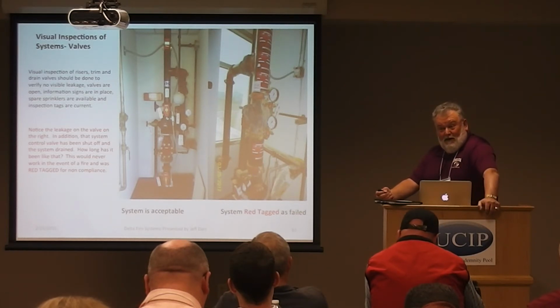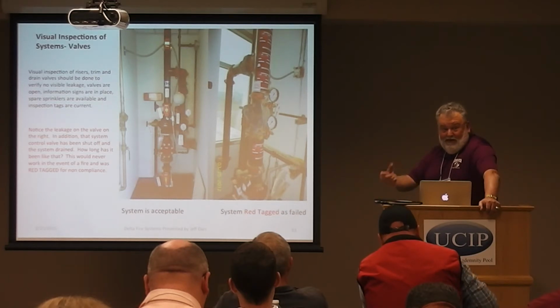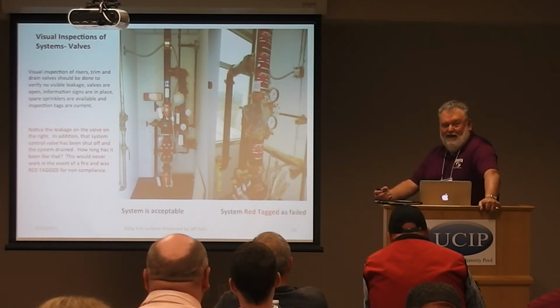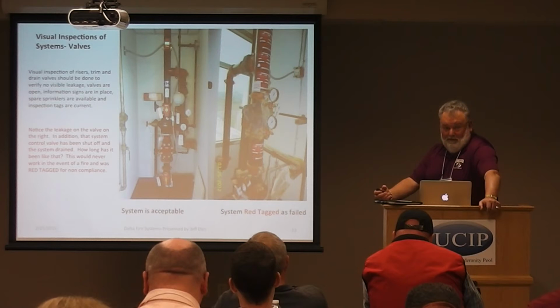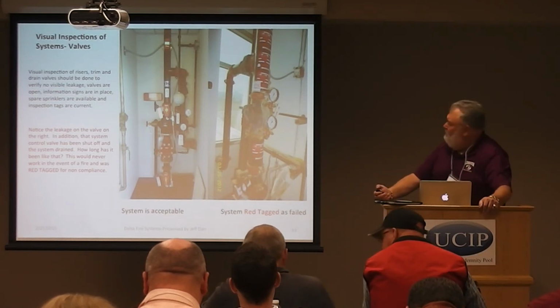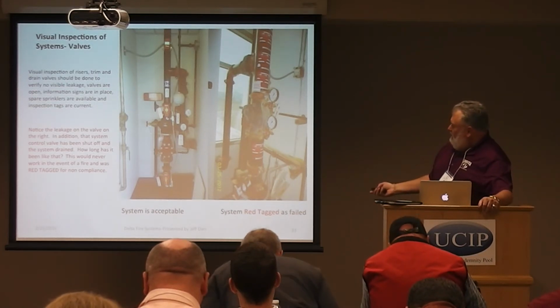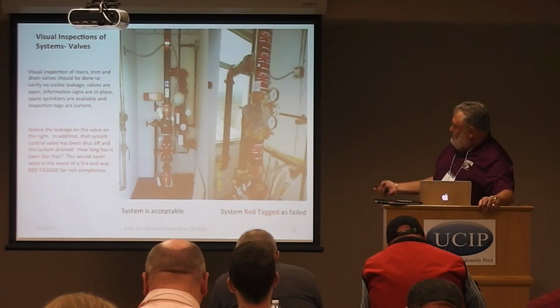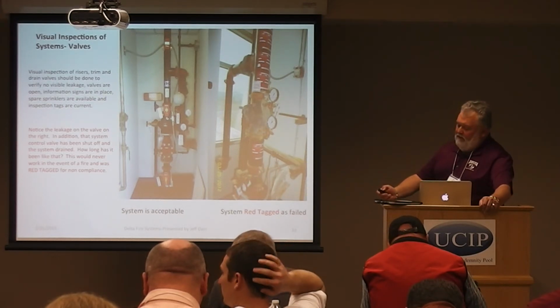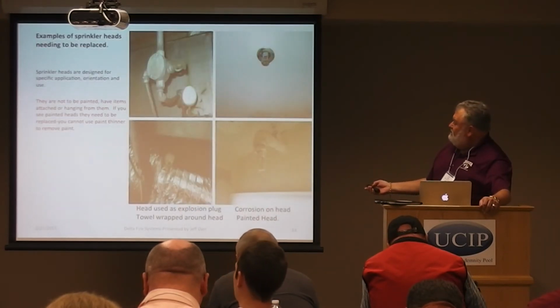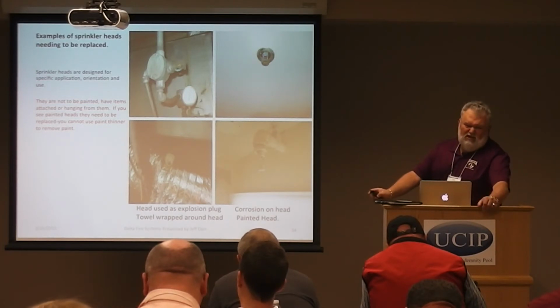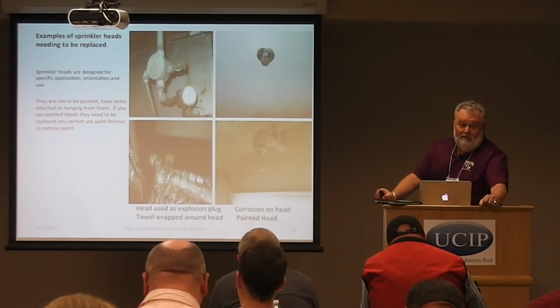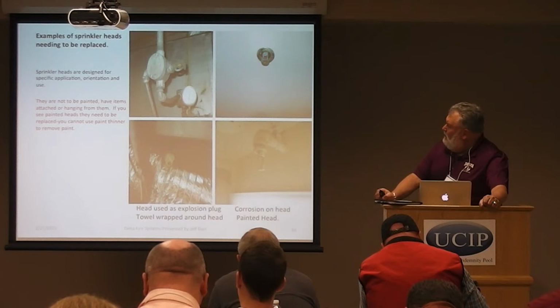Yeah, and just keep in mind, if you have a 2 or 3 story building and that occurs on the first floor, everything above is going to drain out of that head unless you open those drains. That's a good point. Thank you. All right, back to this. Like I said, the one on the right here is what we call a red tag system. And we'll discuss that a little further. That's part of the requirements of the state here.